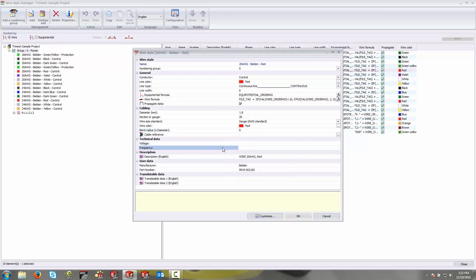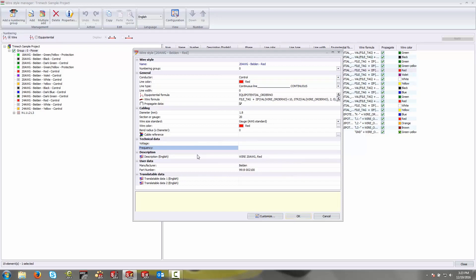Technical data, you generally don't need to fill this out unless there is a particular wire style that is always going to carry the same voltage or frequency. Usually this information here is better fulfilled using the signal property in the specific application of the wire. The signal will only be available when that wire has been drawn on the page, and usually that's going to vary based on application. So I usually leave these two values blank.